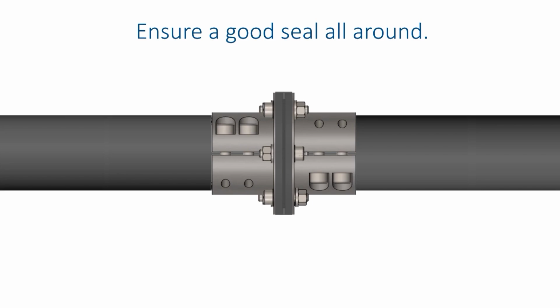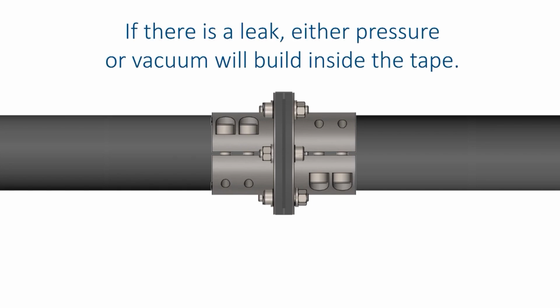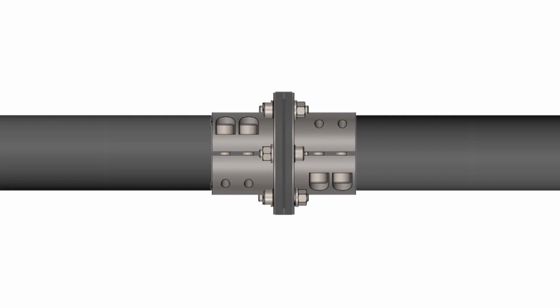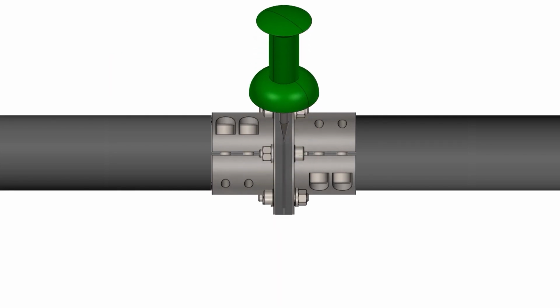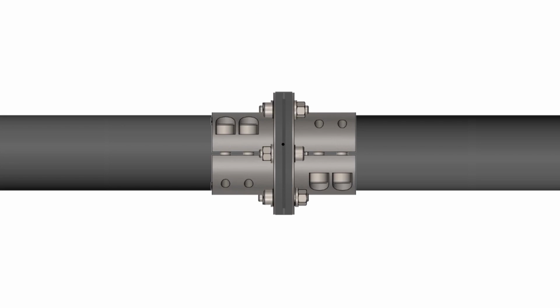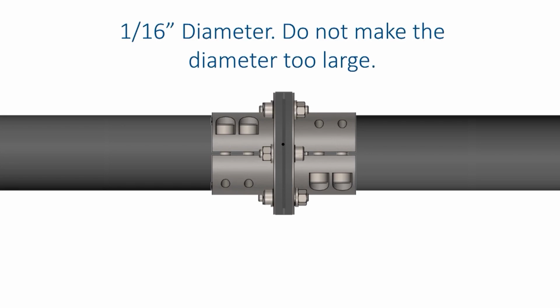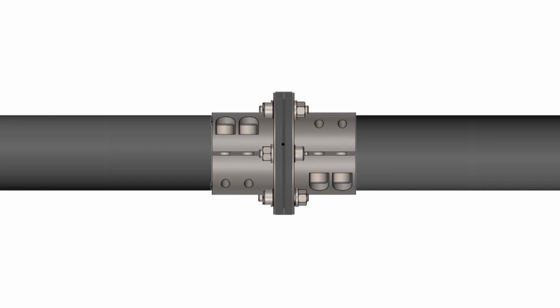Then, wrap the flange with duct tape, making a good seal all around. If there is a leak, either pressure or vacuum will build inside the tape. Next, using a small, sharp point, make a hole in the duct tape, around 1/16 of an inch in diameter. Be careful not to make the diameter too large.